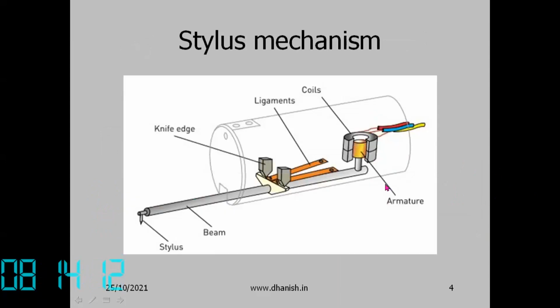So the stylus mechanism is shown here. The stylus is swinging over, it can oscillate over a knife edge up and down. So the stylus is suspended over ligaments. And as the stylus goes up and down, this armature also goes down and up, changing the voltage generated in the coil and thus measuring the position of the stylus. So this is the mechanism of the stylus.